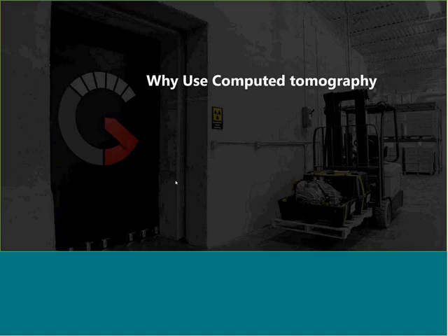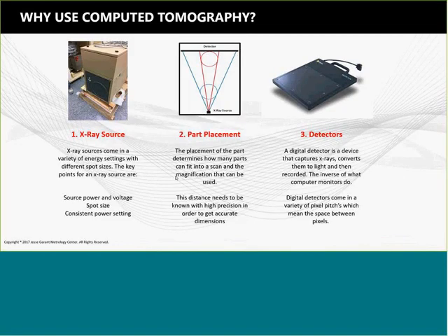Okay. So why would you want to use computed tomography, and what is computed tomography? Well, the actual concept of computed tomography is relatively simple. It's based on 3 components. You have an X-ray source, you have a rotary table for part placement, and then you have a detector.